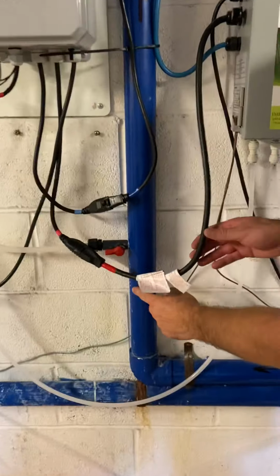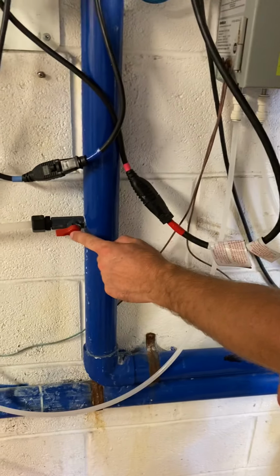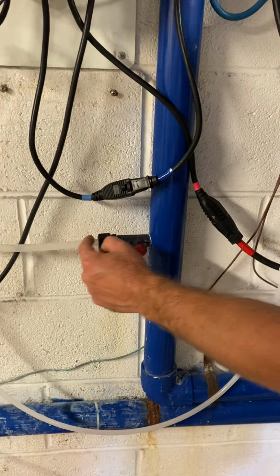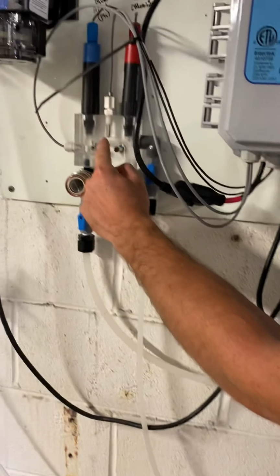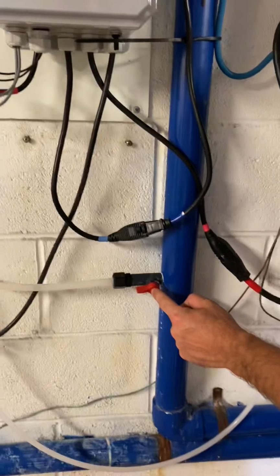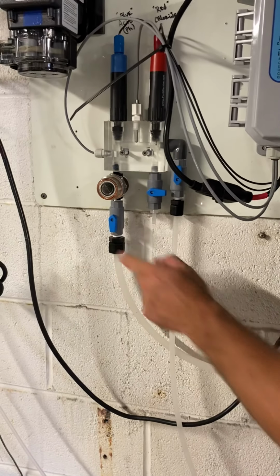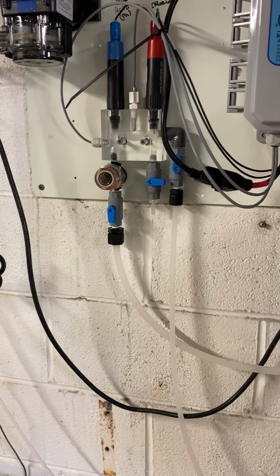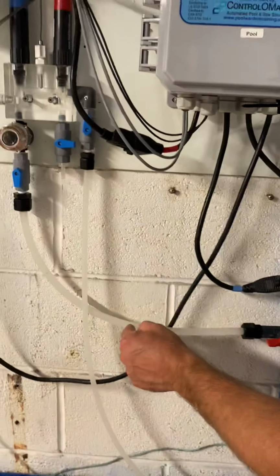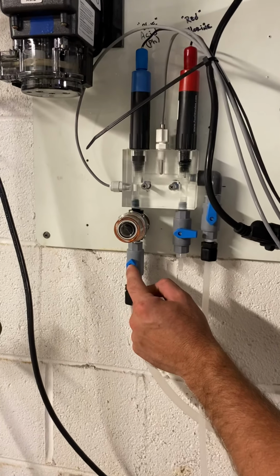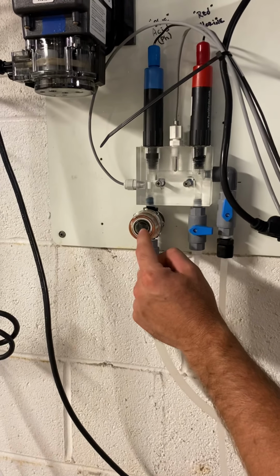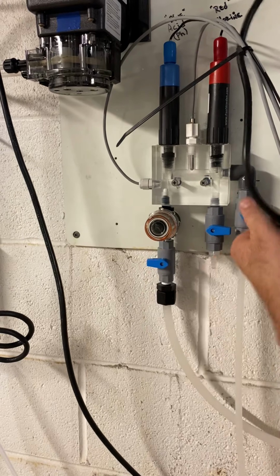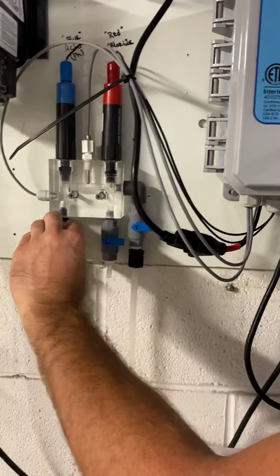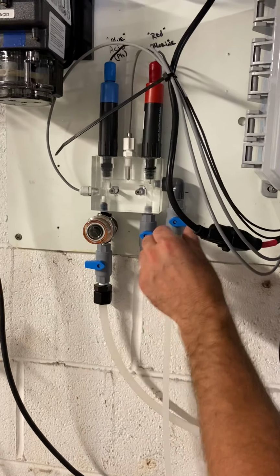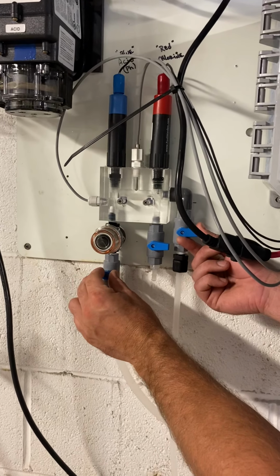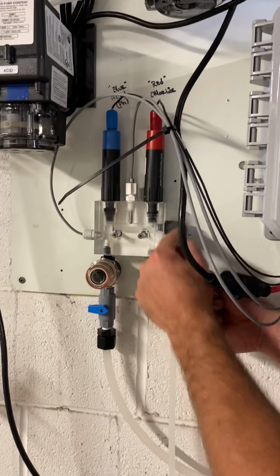So the first thing that we see is we're taking a sample from this pipe going over here and into the flow cell. And as the previous video indicated, these valves are open as well as this. Turning it perpendicular, we'll close it. And what we have here, this is filtered water going in through here. Every once in a while you do still get dirt and debris in here. This can be cleaned out by closing this, loosening that, and there's a little screen in there, you can clear that out. You can see now that we shut that, we lost flow going into this flow cell.